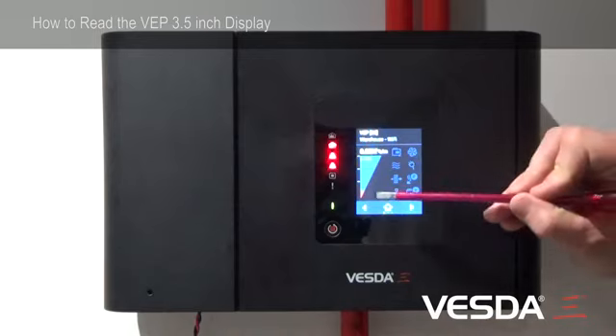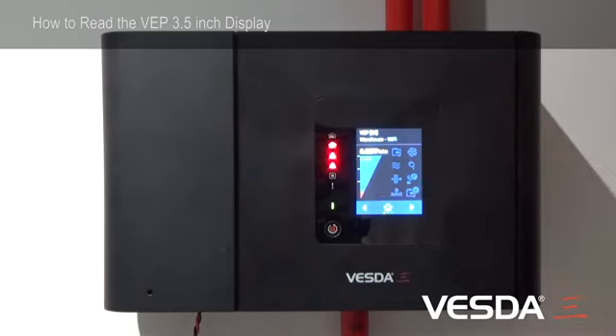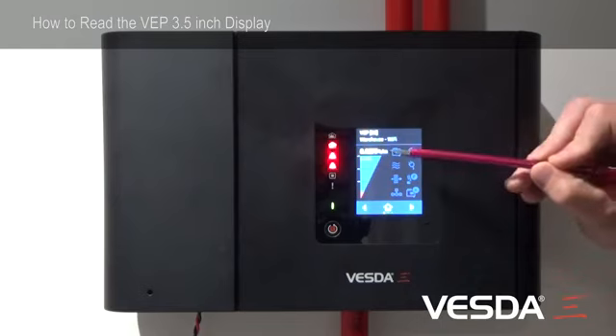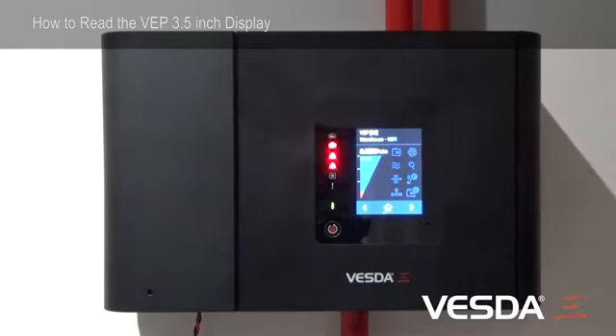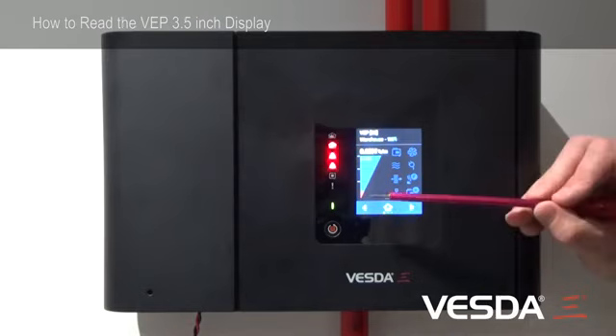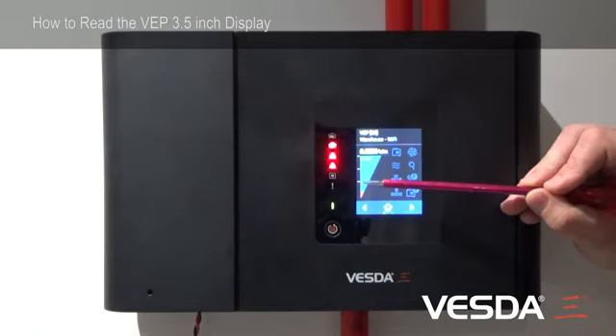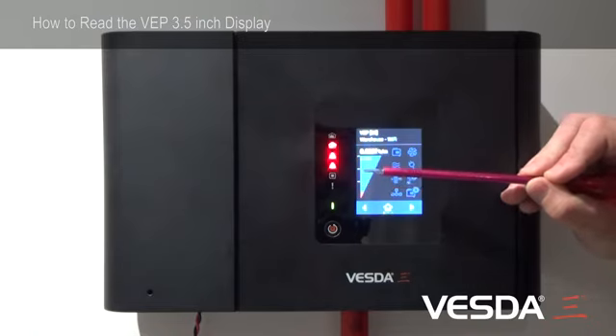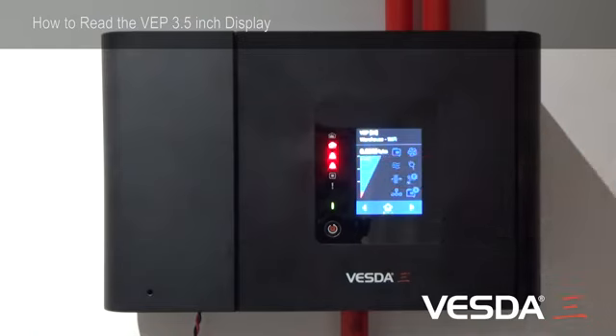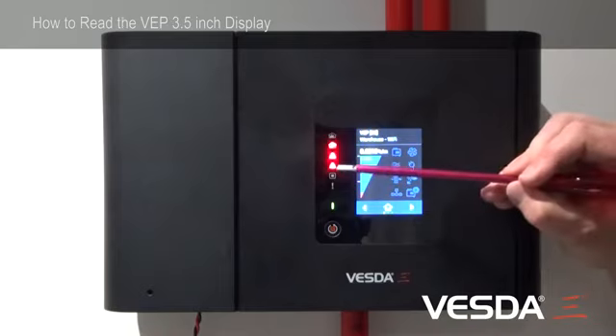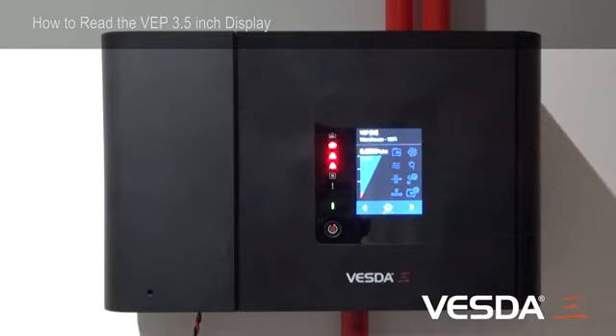Down here you get a bar graph which indicates the smoke threshold. At the moment the smoke reading is at 0.0275% obscuration per metre, and there are 3 alarm levels indicated on the bar graph. The first alarm level at this point here is the alert level, followed by the action level and the fire 1 level. Presently the detector has got some latched alarms on its display, being alert, action and fire 1.